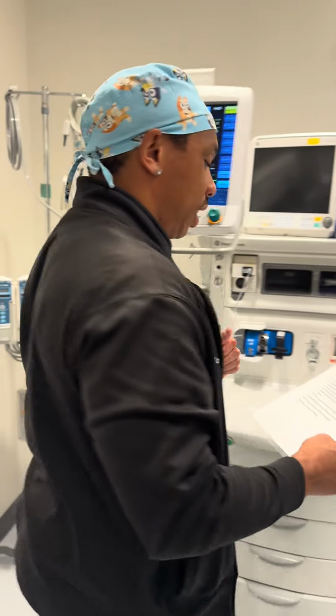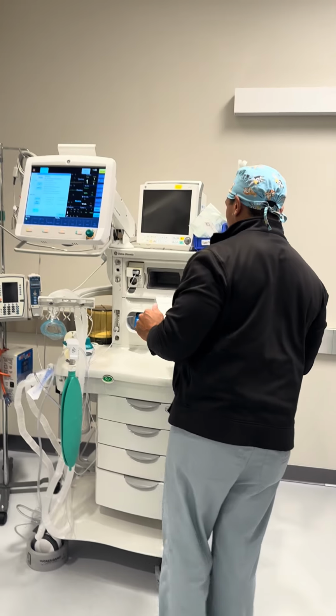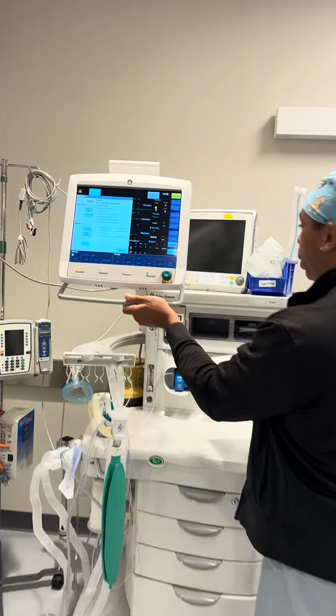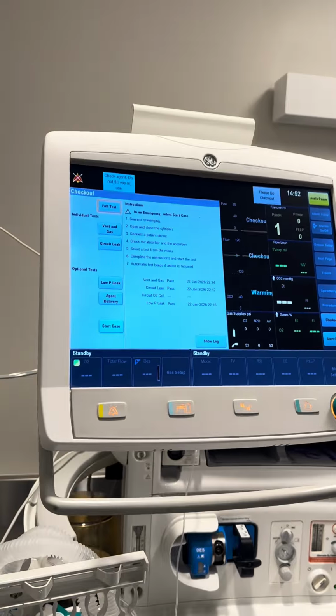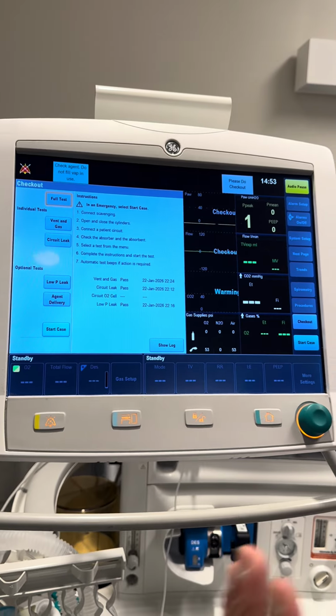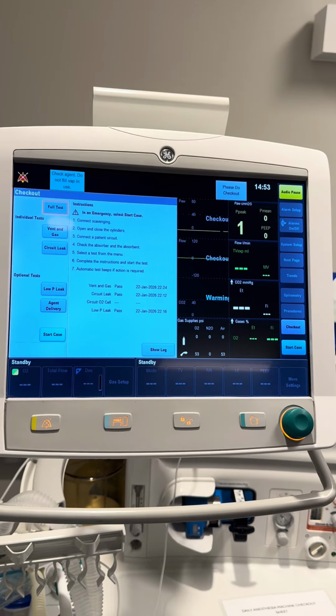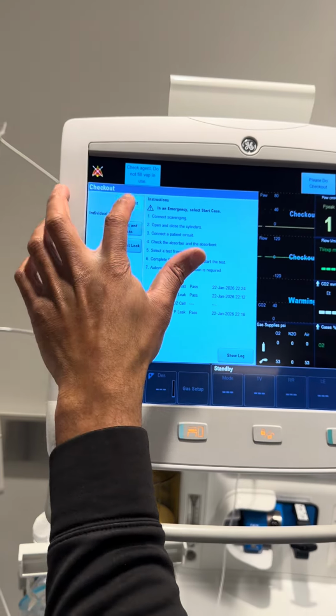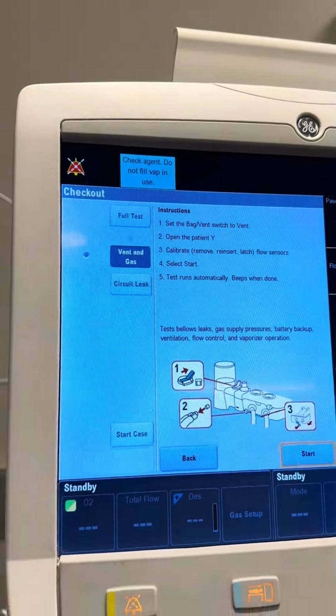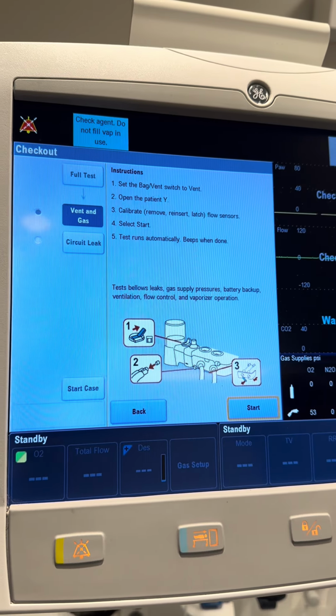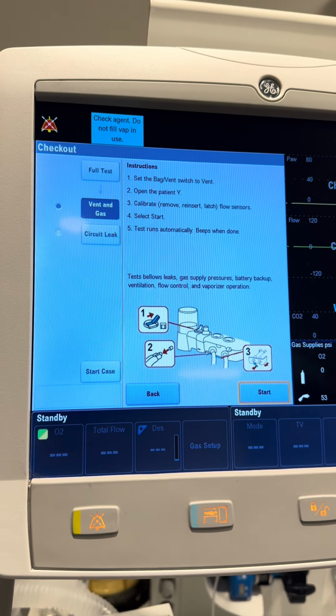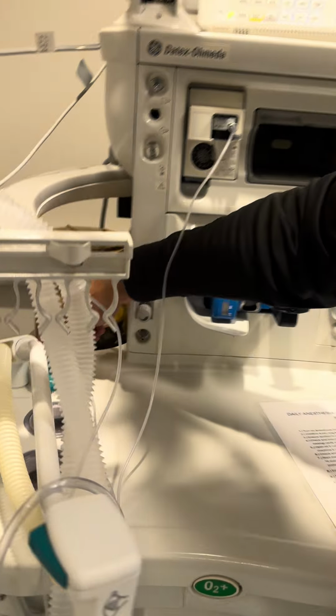So our next step we're going to get into is we're going to start machine check. So from top to bottom, we want to do a full test, right? Because it's been 24 hours and we're at the start of the day, you just started your shift. So we're going to hit full test. You'll see the steps that pop up on the screen. So we're going to do as such. It says set the bag vent to vent. So you're going to switch it to vent.